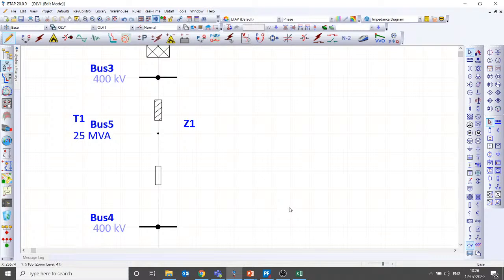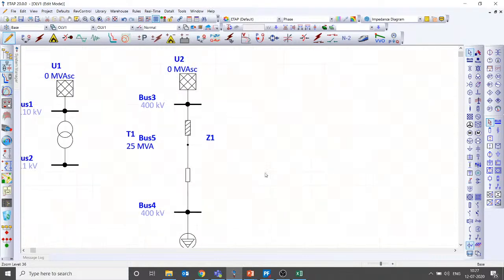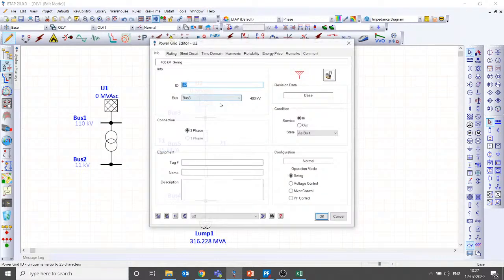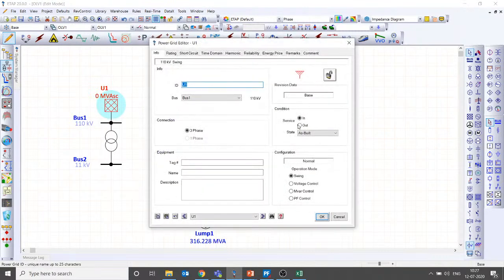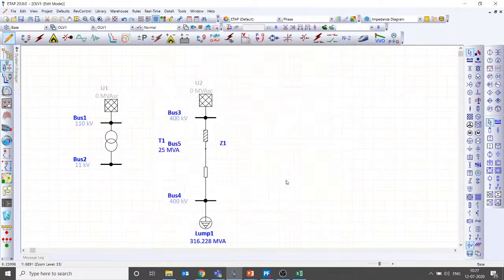Parthiban asks: my system has only a generator, no grid connection. In which mode should the generator be operated? Swing, voltage control, MVAR control or power factor control? It cannot operate in MVAR control or power factor control. So to simulate your case, let me switch off both the generators. Let me take a small example.